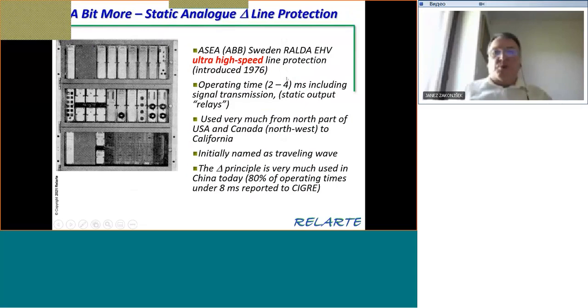And what is important, in order to get this very short tripping or operating time, they were already during that period using static outputs. I can say relays, although they were not relays. They were transistors and electronic outputs. So this protection was used very much on lines going from the northwest of the United States and Canada down to California. And at the beginning, they were calling it traveling wave protection.